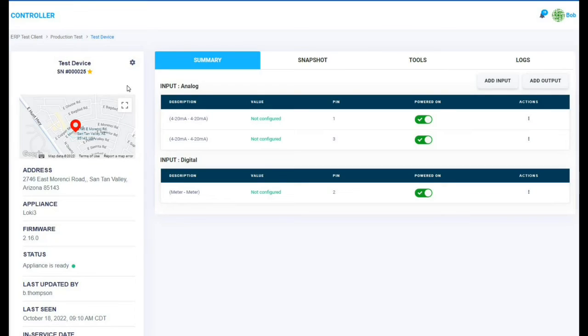Now that we've shown you how to hook up a Modbus probe, let's show you how to program one into your controller. As you can see here, I've already added two analog probes onto my controller, and I have a dry contact probe that I've added, which is simply a flow meter.